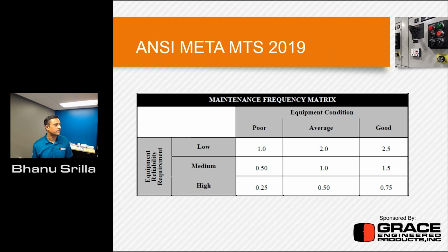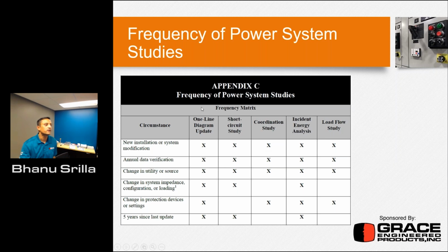This is one of the charts, because most of the time people ask how often or how frequently they need to do this. This is a good guideline. I took a few snapshots from the ANSI NETA standards. This is the maintenance frequency matrix. You evaluate the equipment based on criteria, such as equipment condition. You know how your equipment is, right? Before you start your car, you know the condition of your car. The same way with your equipment. You can self-rate your equipment as poor, average, or good, and then take the scores. For reliability requirements, if you're looking at medium or high reliability, you take the 0.75 or 1 score, and then apply it to the slides I'm showing here. So there is a new installation or system modification.